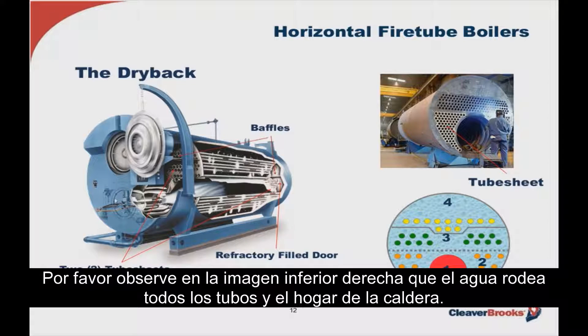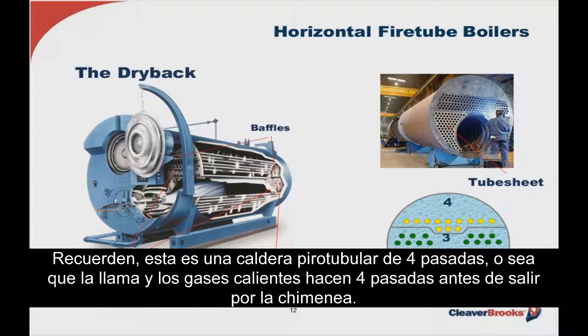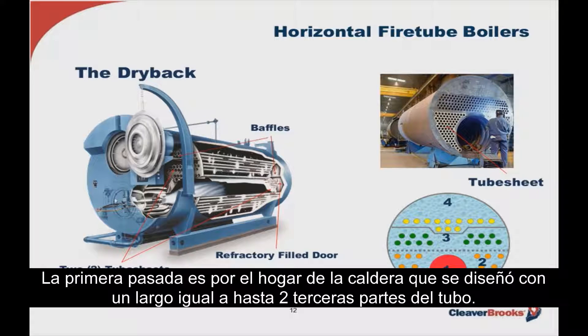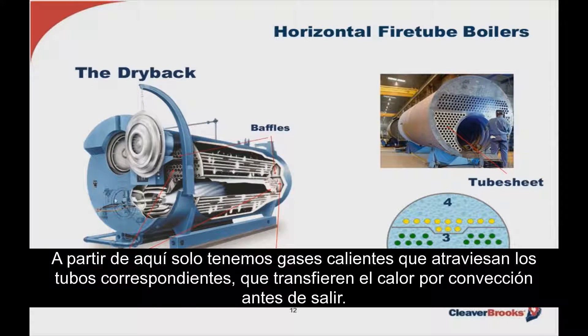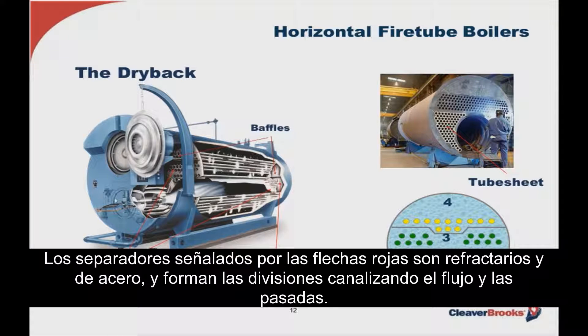In a four-pass fire tube boiler, the flame and hot gases make four distinct passes before exiting out the stack. Starting with the furnace as the first pass, the burner has been designed to match the volume and length of the furnace, allowing the flame to extend only about two-thirds of the way down it. From there, hot gases traverse through the respective tubes, convectively transferring their heat before exiting. Baffles — both refractory and steel — form the divisions channeling the flow between the passes.